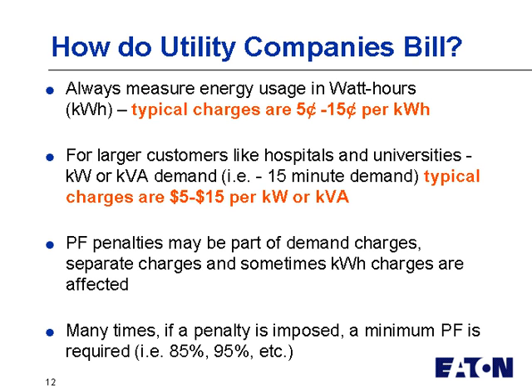And that's a one time a month charge, and the charge is typically $5 to $15 per kilowatt or kVA, for example. Now, additionally, they may put power factor penalties, and they may be part of a demand charge, or they may be a separate charge built into, for example, even the kilowatt-hour charges. And sometimes, again, the utility company will try to incentivize the customers to actually install power factor correction by giving a minimum threshold for power factor, and they'll say something like you need to have an 85% or 95% power factor maintained, otherwise we will charge a penalty.